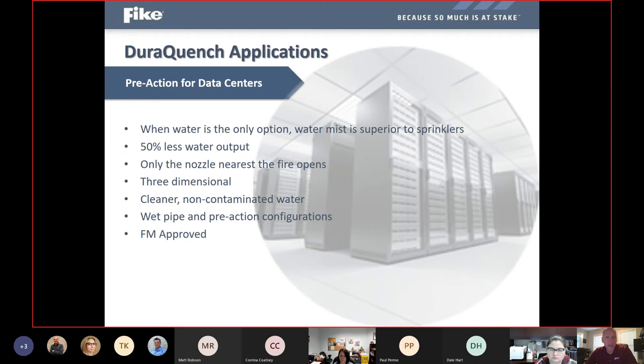But even when they do that, a lot of times they still need to have a sprinkler system as a fail-safe backup. So if they have to have that sprinkler system regardless, we can give them an option: you have to have water regardless, so how about if it ever has to discharge in there, let's have it be a mist instead of a sprinkler system, so it can quickly extinguish and do a heck of a lot less collateral damage. It's a very easy sale and understanding as to what the benefits are to have mist. And we are now listed for pre-action systems, even designed as a pre-action dry pipe system as well.